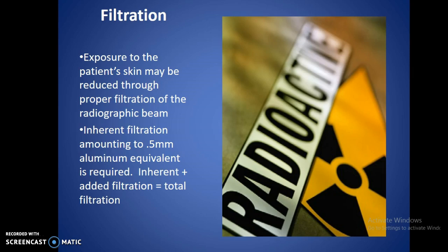Exposure to the patient's skin may be reduced through proper filtration of the radiographic beam. Inherent filtration amounting to .5 millimeters of aluminum equivalent is required. Inherent plus added filtration equals total filtration. We went over filtration a little bit in the prior chapter as well.